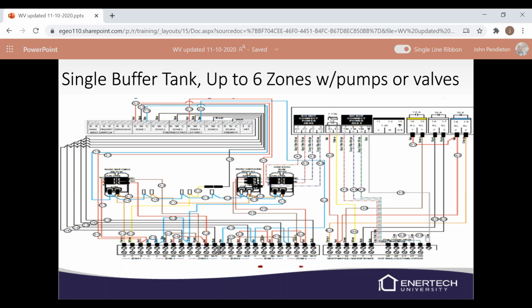Here's a single buffer tank up to 6 zones with pumps or valves. With your radiant zones, you can pump them or you can use valves, and we have a setup for that as well. This is going to use HBX control as well.